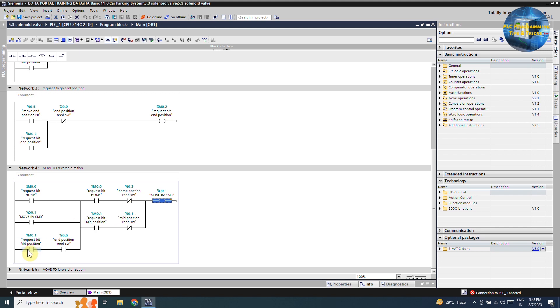Next, if the request for the mid position m0.1 bit turns on and the cylinder is at the end position right now, it will latch on the reverse command output Q0.1. This will bring the cylinder from the end position to the mid position sensor. When the cylinder reaches the mid position sensor i0.1, this contact opens and unlatches the Q0.1 output and the cylinder stops at the mid position.